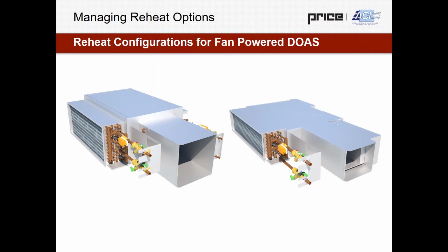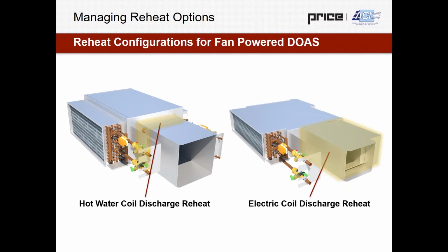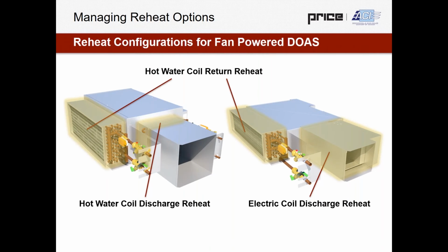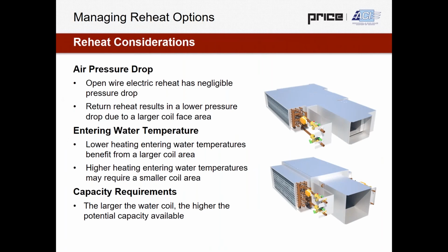So there's lots of different possible ways to be reheating air with this equipment, whether that's the typical hot water coil on the discharge, an electric coil on the discharge, or even a hot water coil on the return of the unit. That can be an additional coil accessory sitting outside of the sensible cooling coil or inside the sensible cooling coil as well. Either is an option. Or it could potentially be a hot cold changeover application, which would be far less common, but definitely something we can offer. And there's lots of considerations when you're looking at selecting this reheat.